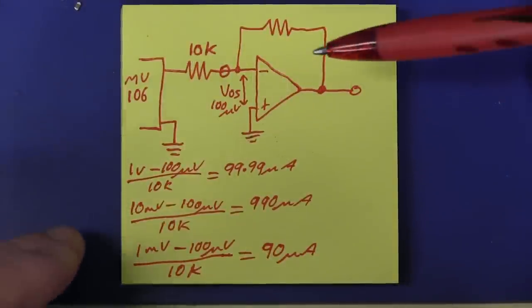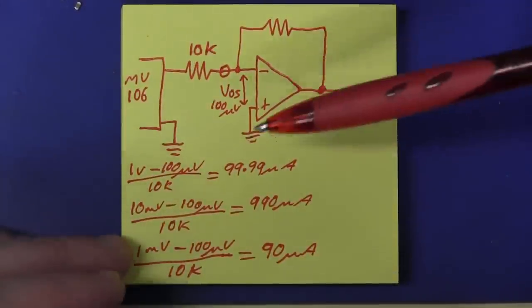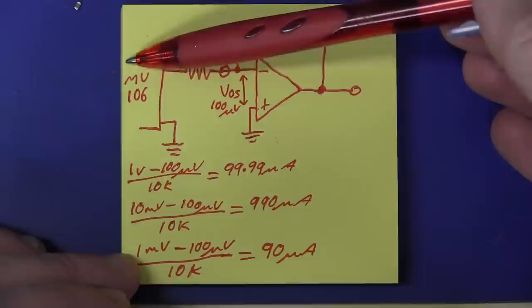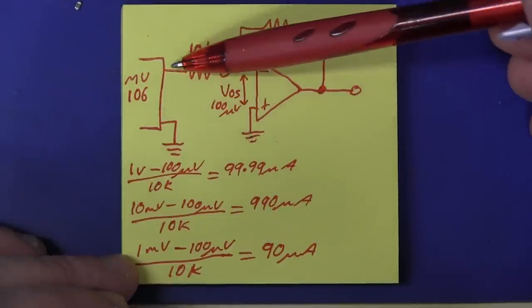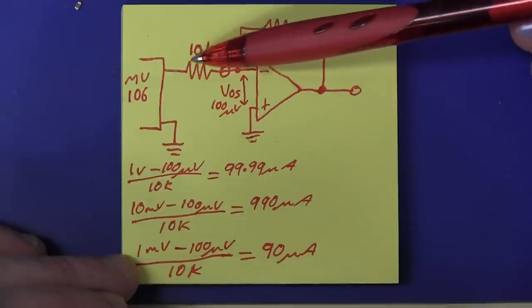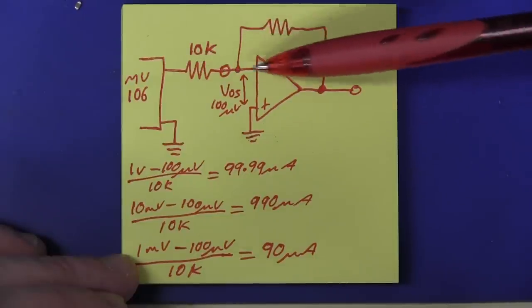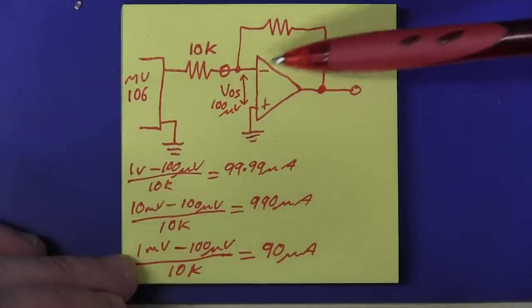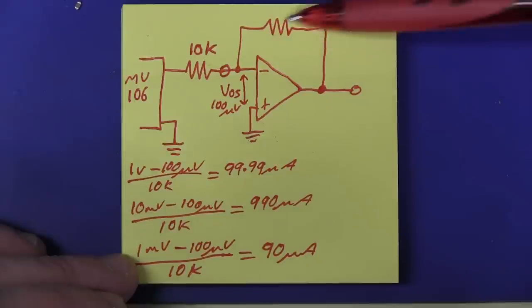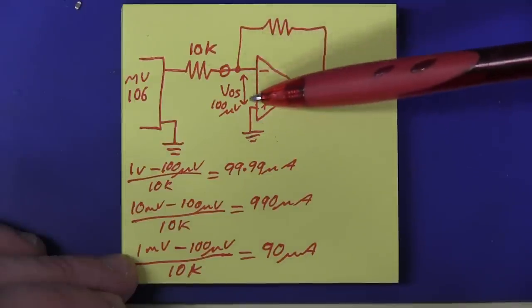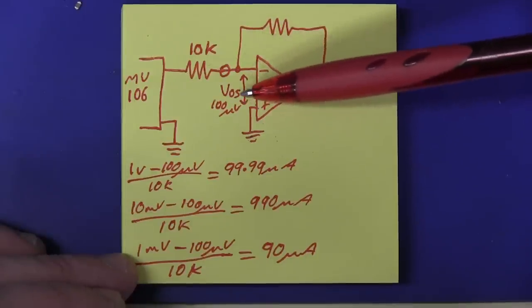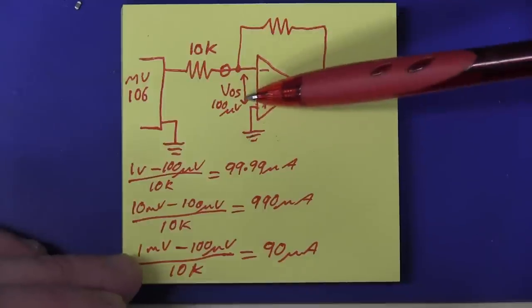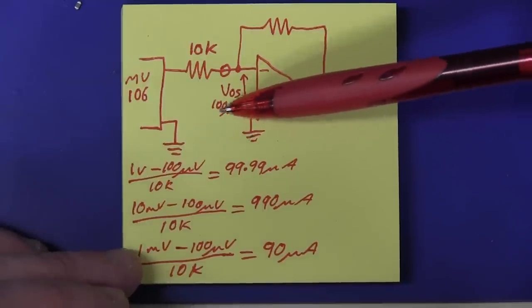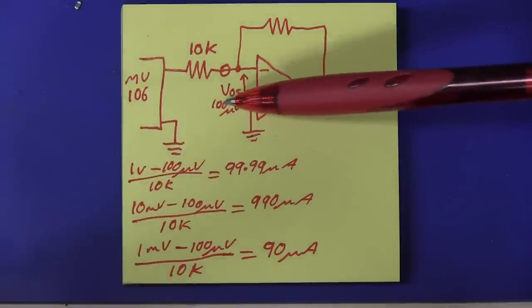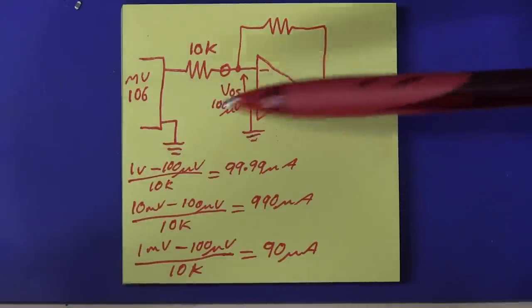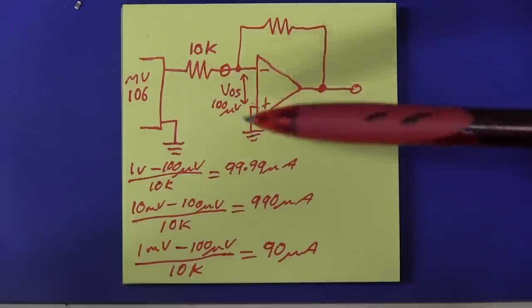And if we take a look at this DaveCAD drawing here, we can see exactly what's going on. We've got our MV106 voltage standard generating our test voltage here. We've got our 10K series resistor going into our feedback amplifier here. Now, at the moment, let's just ignore the feedback resistance here, and we've got that measured VOS, or offset or burden voltage there, of around 100 microvolts. Let's just round it to 100 microvolts. It's going to change per range and all that sort of stuff, but let's just take that as a value.